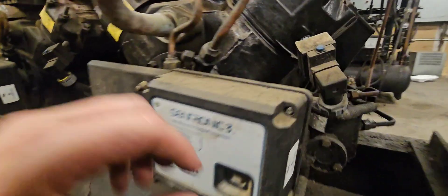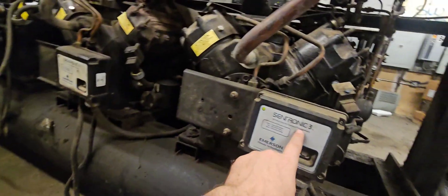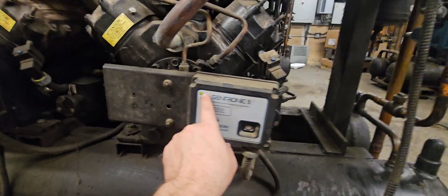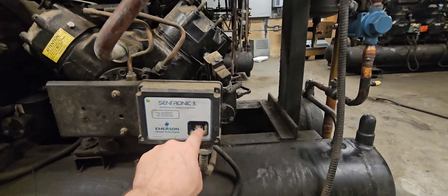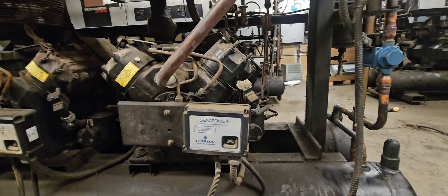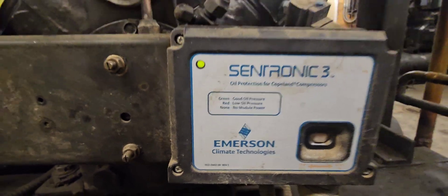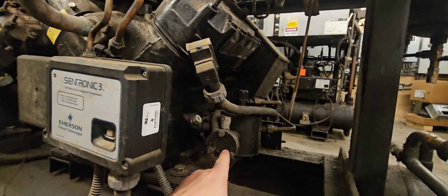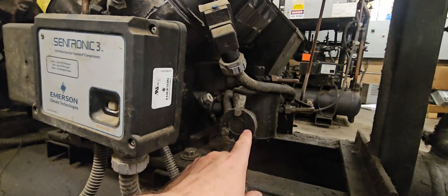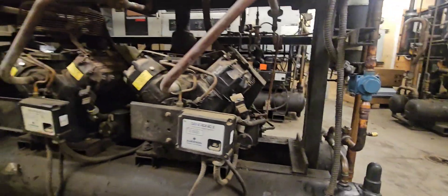This is a Sentronic 3. It uses a transducer right here. It uses that transducer from the Sentronic, and once this drops below 9 pounds net oil, it starts to time out. That light turns red and it times off for 120 seconds. If it stays under 9 pounds, it trips that oil protection. Green is good, red is bad, no light means no power. Additionally, we have our oil float — or just a float, some people call it a pot. Really it's called an oil level control, made by Sporlan most of the time. Those are the ones I like — the Sporlan ones. I see a lot of the Henry ones, those blue ones.